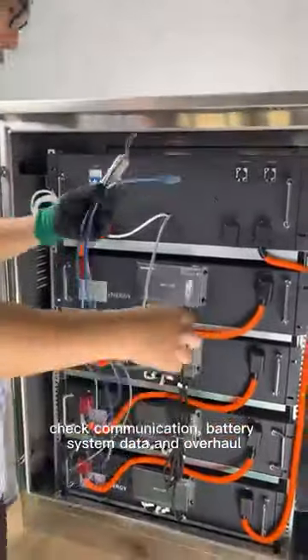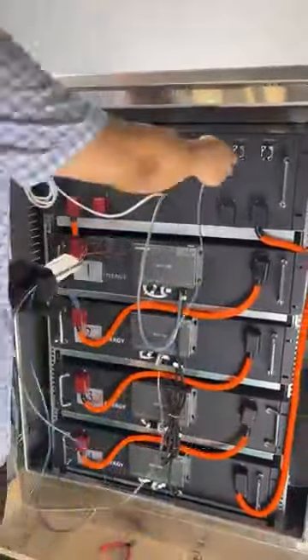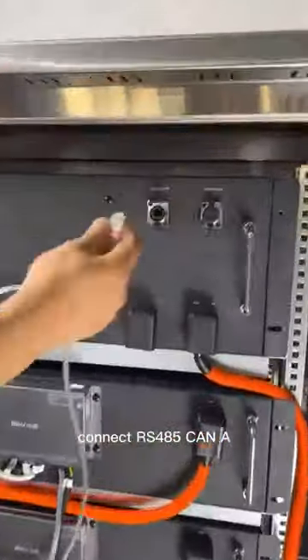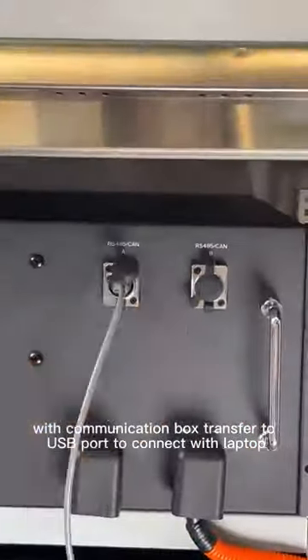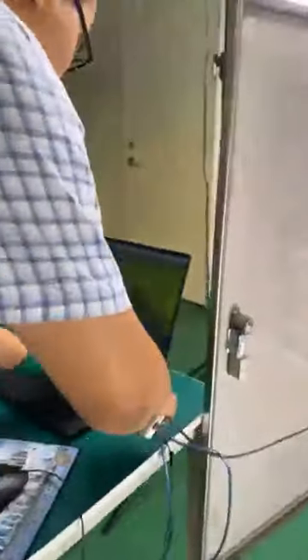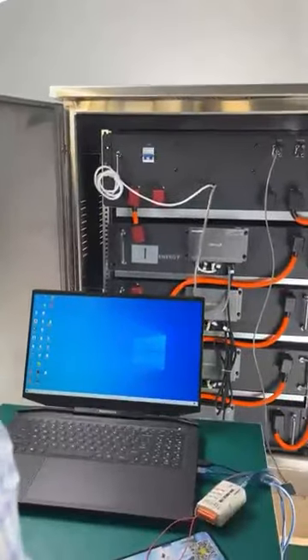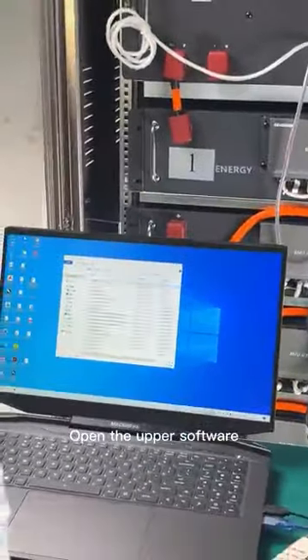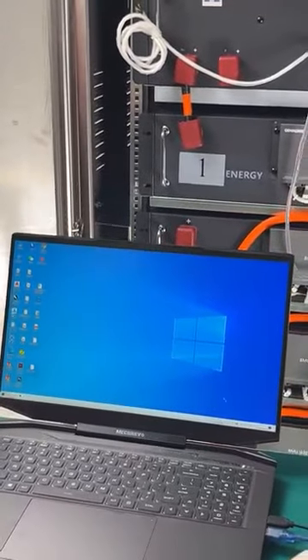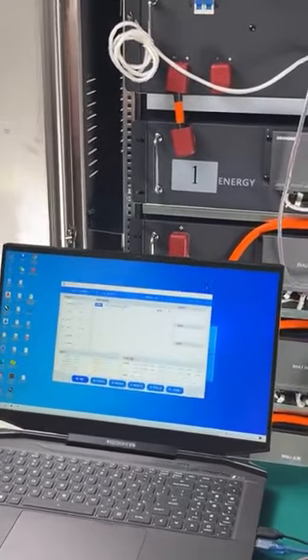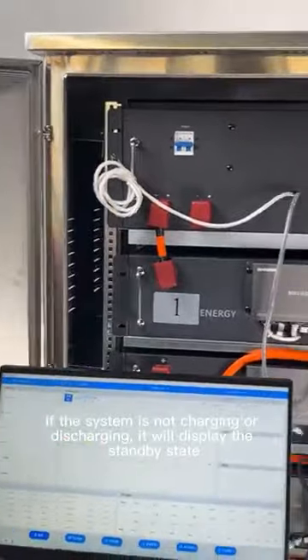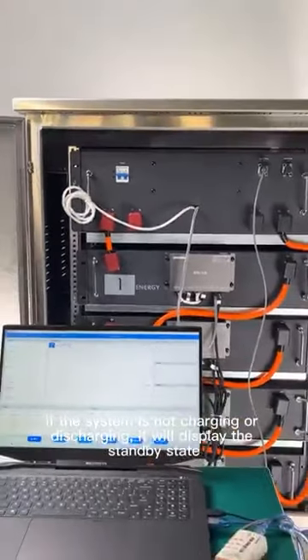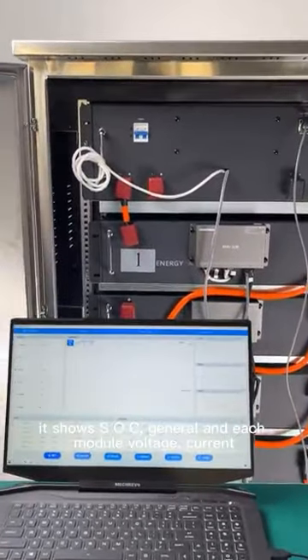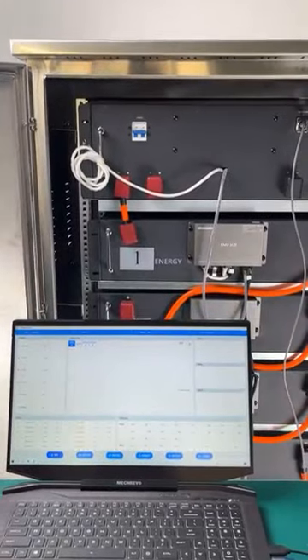Check communication, battery system data and overhaul. Connect RS485 CAN A with communication box transfer to USB port to connect with laptop. Open the upper software. If the system is not charging or discharging, it will display the standby state. It shows SOC, general and each module voltage, current.